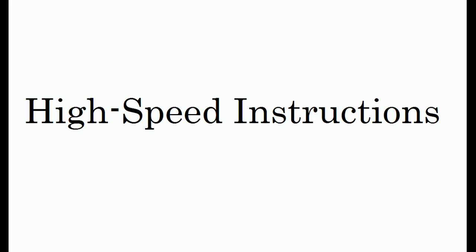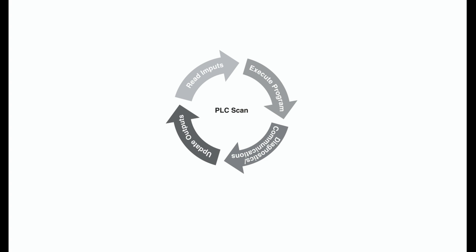High-speed instructions. As discussed earlier, PLCs have a scan time. The scan time depends on the size of the program, the number of inputs or outputs, and the amount of communication required. Events may occur in an application that require a response from the PLC before the scan cycle is complete.